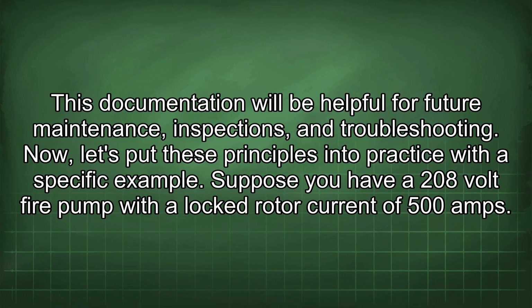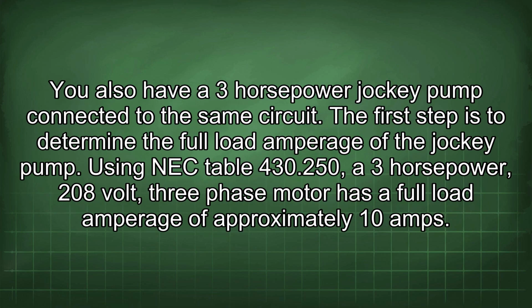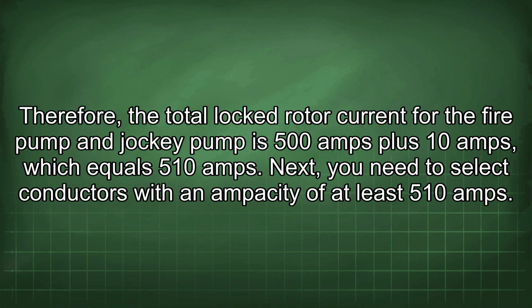Suppose you have a 208-volt fire pump with a locked rotor current of 500 amps. You also have a 3 horsepower jockey pump connected to the same circuit. The first step is to determine the full load amperage of the jockey pump. Using NEC Table 430.250, a 3 horsepower, 208 volt, 3-phase motor has a full load amperage of approximately 10 amps. Therefore, the total locked rotor current for the fire pump and jockey pump is 500 amps plus 10 amps, which equals 510 amps. Next, you need to select conductors with an ampacity of at least 510 amps.